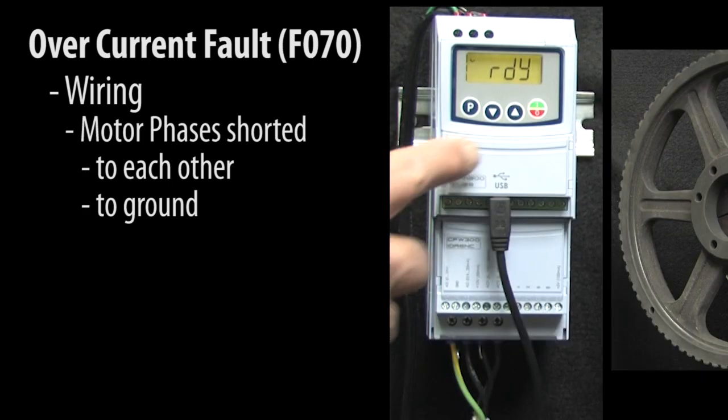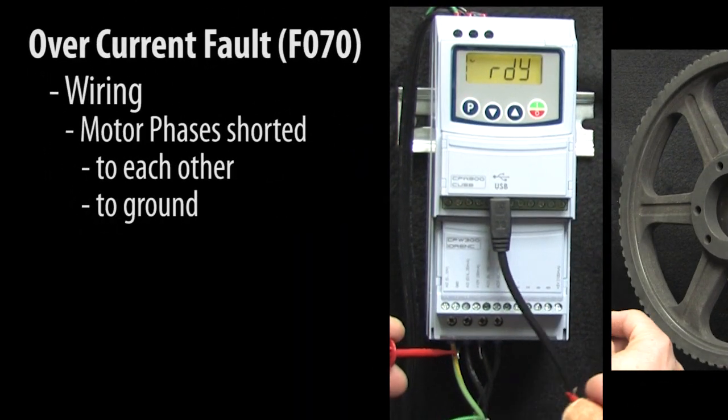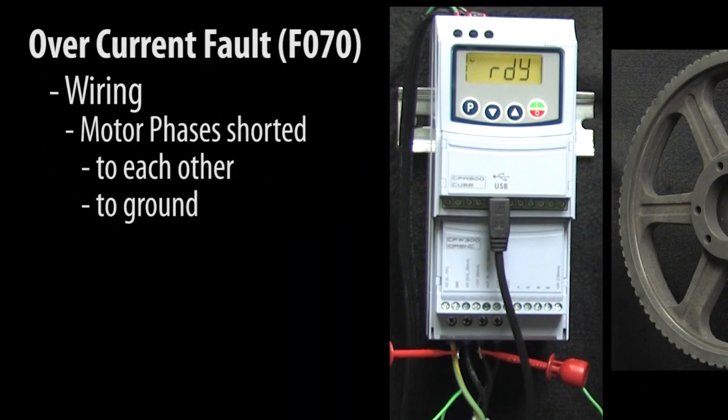For example, if I hit run, the drive spins the motor up to speed just fine. But if I use a clip lead to short two of the motor phases and then hit run, the drive sees the issue, immediately shuts down the output to prevent damage to the system and issues an overcurrent fault code.